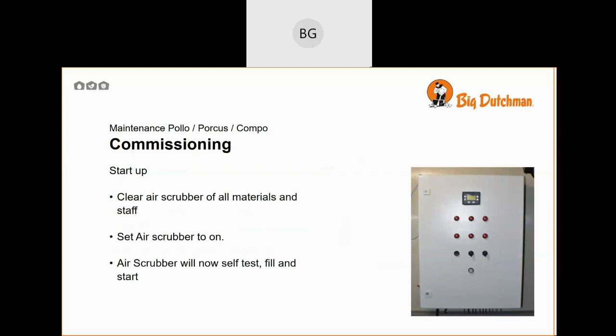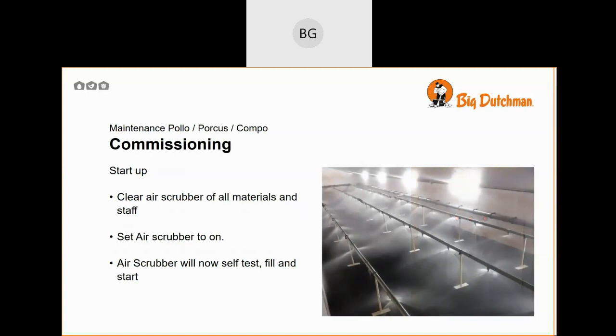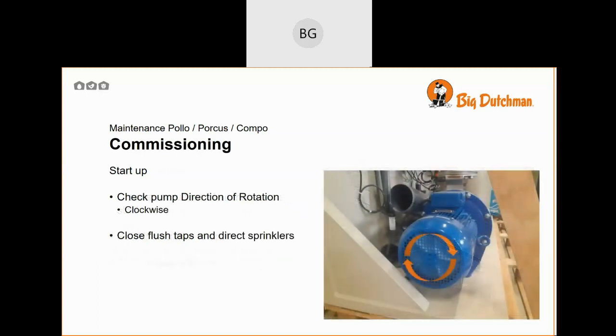Start up. Clear the air scrubber of all materials and staff. Set the air scrubber to on. The air scrubber will now self-test, fill, and start. The first check is to check the direction of rotation of the pump. This needs to be clockwise.